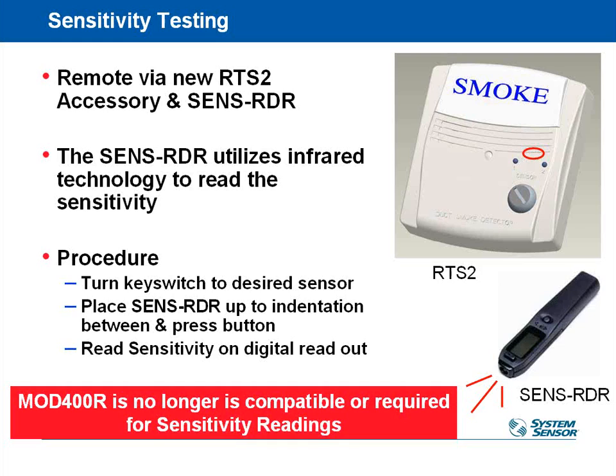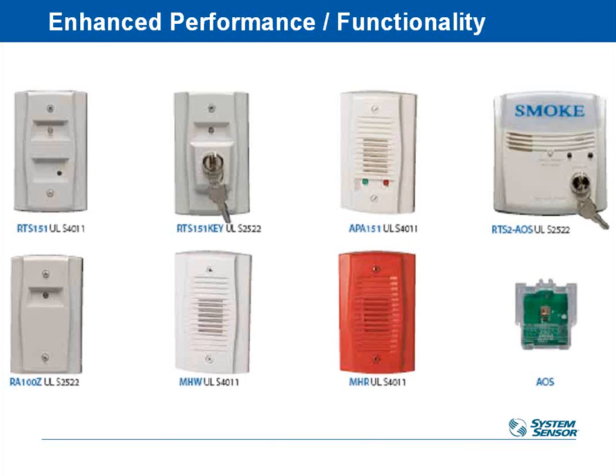There's a sensitivity measurement tester that you can use with it. This is probably more for the fire life safety guys and less for the mechanical contractor world, but it is available. If you're using that test station, you can take this tester and put it right up to the front of it, put the key switch on the one you want to test, and then it'll read back to you the sensitivity level on the digital readout of the detector itself. So it does it via communication.